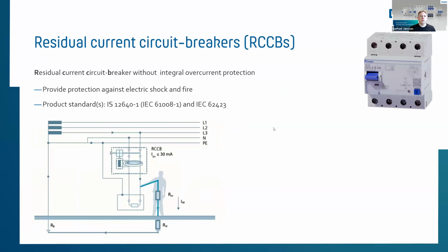Starting with the RCCBs, residual current circuit breakers. Those have no overcurrent protection, only fault protection. They provide protection against electric shock and fire. That means they can also provide personal protection, with around 30 milliamp residual current. The product standards in India and the IEC standard correspond a bit. You see them here in the second bullet point.